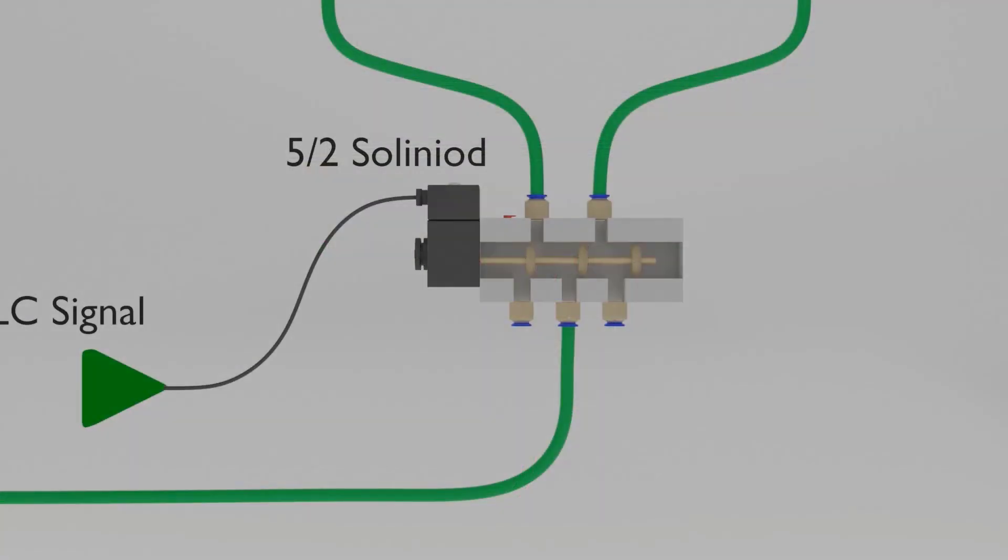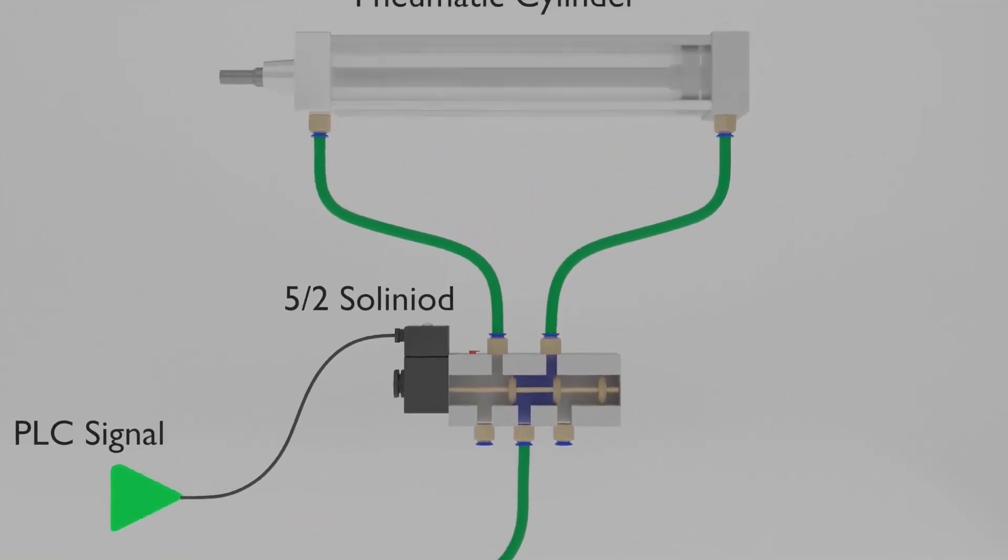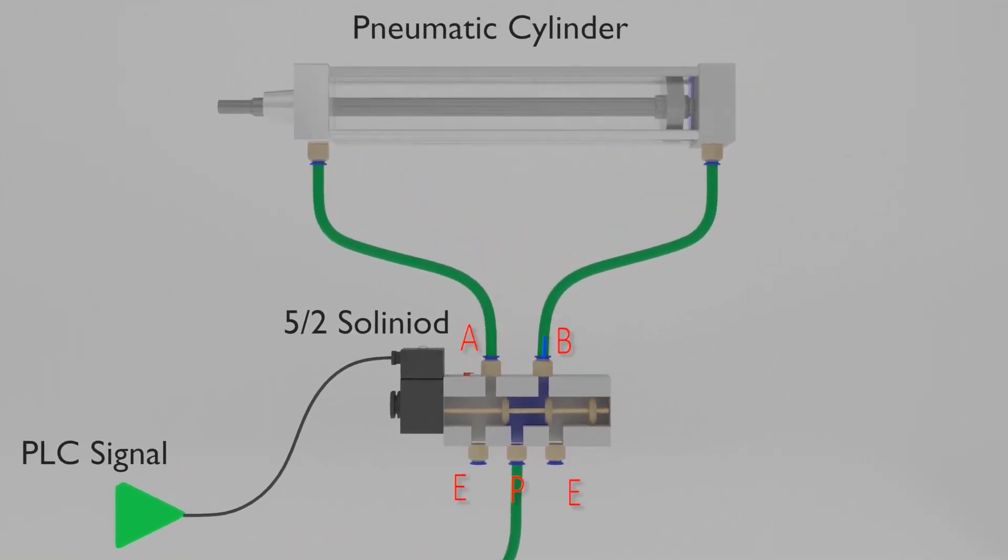When the PLC signal energizes the coil of the solenoid valve, its spool moves and links the pressure port with port B of solenoid valve and port A with the exhaust port. This way compressed air moves towards port B and through pipe it enters the back port of the cylinder. As the compressed air exerts the pneumatic pressure on the piston of the cylinder shaft, it starts to move forward because of the force of compressed air.